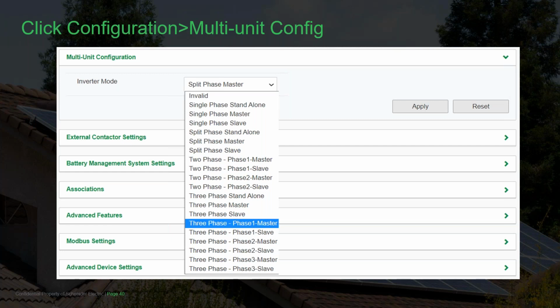Each XW Pro has a dedicated configuration menu. Navigate to Advanced Multi-Unit Config and select 3-phase Phase 1 Master from the drop-down menu for inverter number 1, typically the leftmost inverter. However, physical order is irrelevant. Click Apply. You can see there are many selections in the multi-unit config menu. We typically only use the split phase and the 3-phase options. The others are just placeholders for future development.